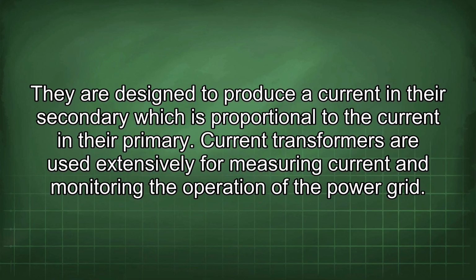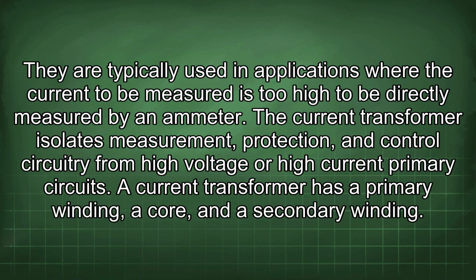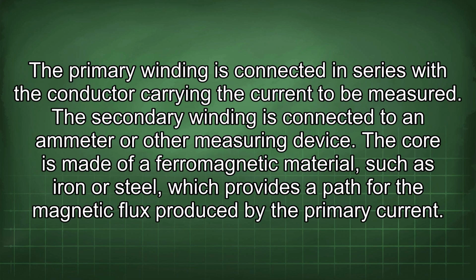They are designed to produce a current in their secondary which is proportional to the current in their primary. Current transformers are used extensively for measuring current and monitoring the operation of the power grid. They are typically used in applications where the current to be measured is too high to be directly measured by an ammeter. The current transformer isolates measurement, protection, and control circuitry from high voltage or high current primary circuits. A current transformer has a primary winding, a core, and a secondary winding. The primary winding is connected in series with the conductor carrying the current to be measured. The secondary winding is connected to an ammeter or other measuring device.